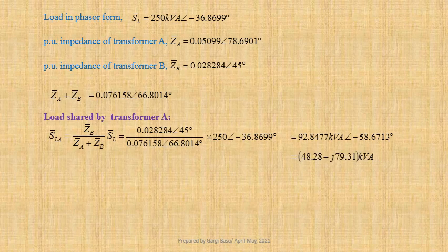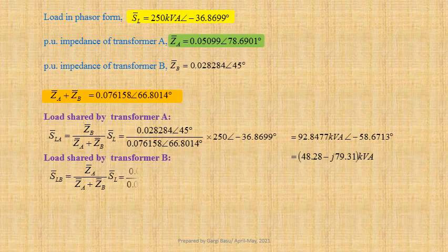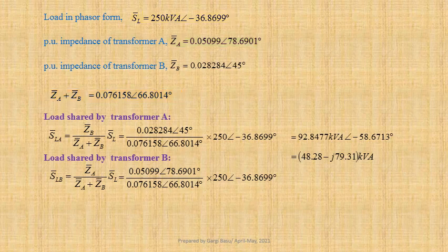Let us now determine load shared by transformer B. SLB equals ZA divided by ZA plus ZB into SL. Using values we get 0.05099 at an angle 78.6901 degree divided by 0.076158 at an angle 66.8014 degree into 250 at an angle minus 36.8699 degree.